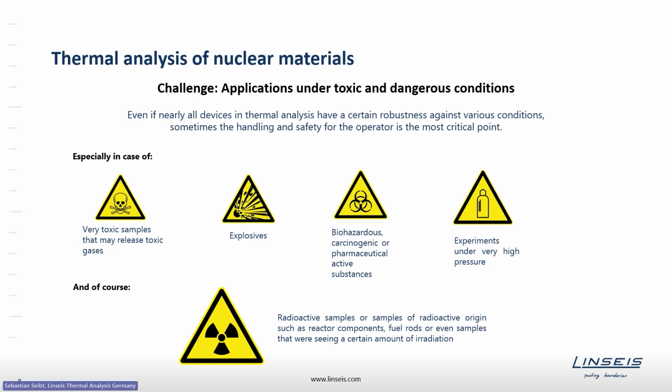there is a need to take that into account when the instrument is designed. For some toxic or explosive samples, it's maybe enough to focus on the sample chamber, but for more critical and more dangerous material, it might be useful to think about the complete instrument design, which we are doing, and that's the reason why we are doing these special versions.